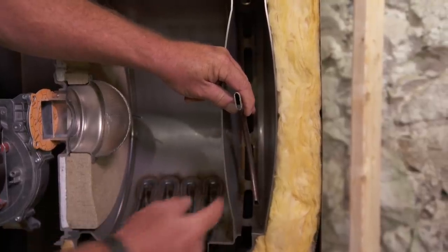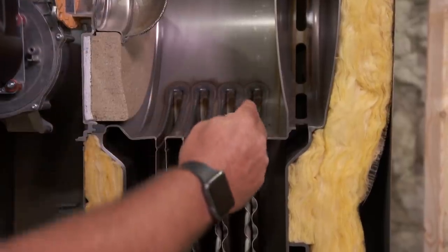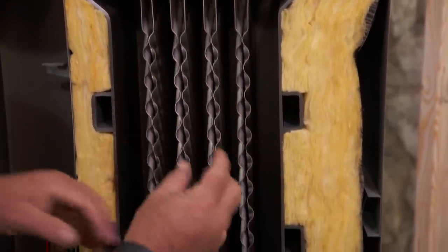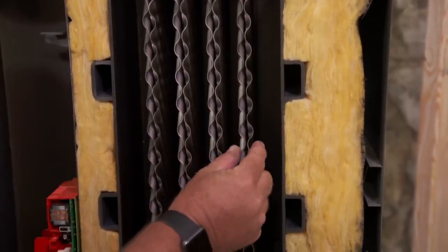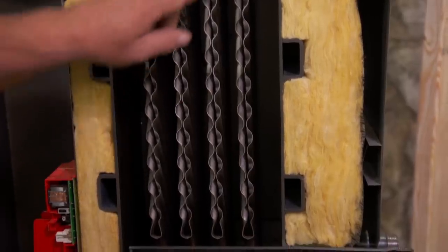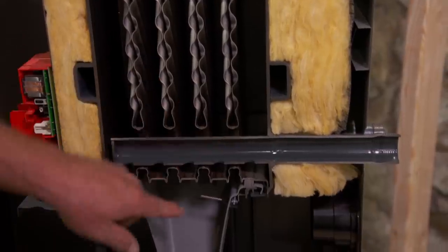Look at the difference in water quality — there's no real place for sludge to collect. The burner comes on and drives downward, not upward, down through these heat exchanger sections right here. These are crosshatched and they squeeze all the heat out. There's plenty of water right here to take all that heat away, and by the time it gets to the bottom, there's hardly any temperature left.